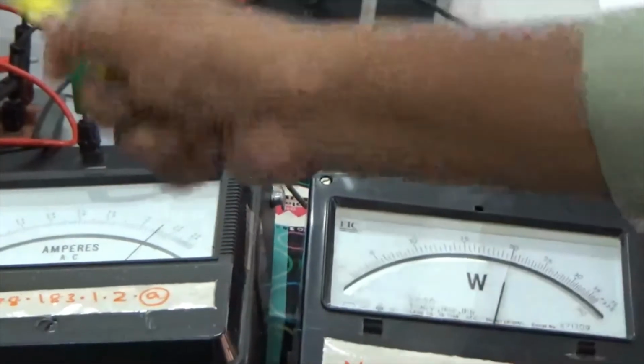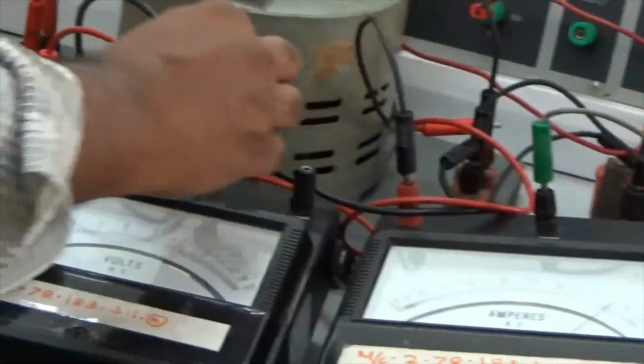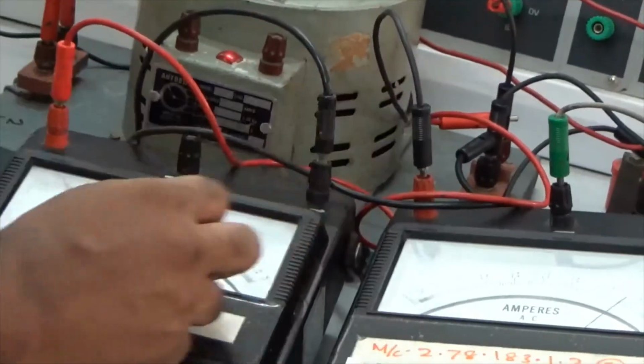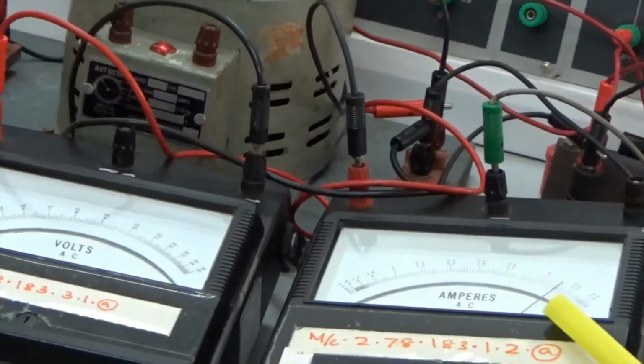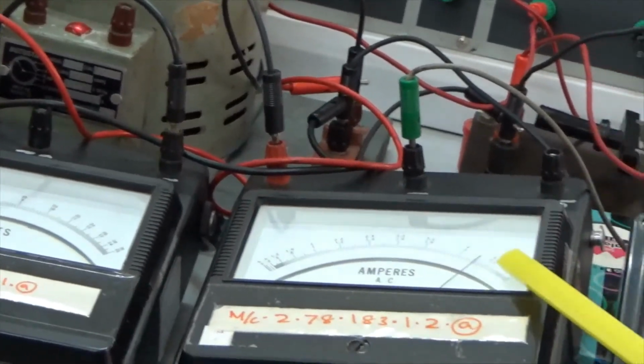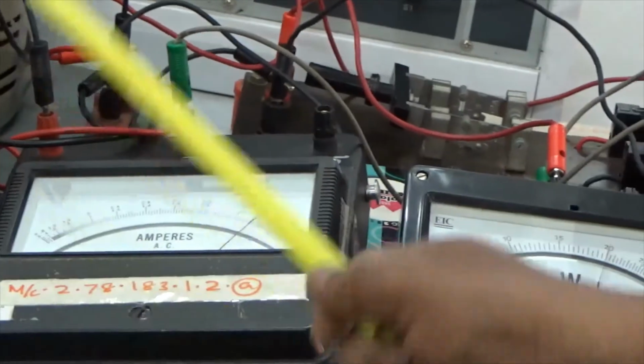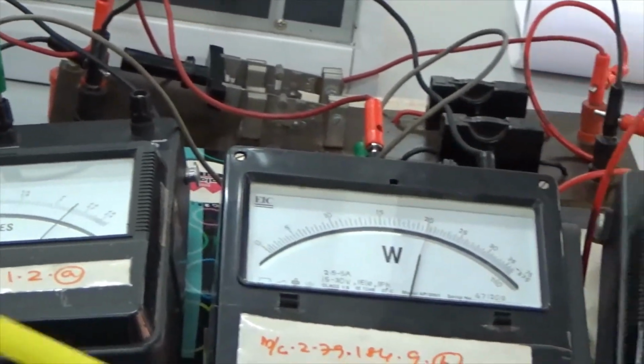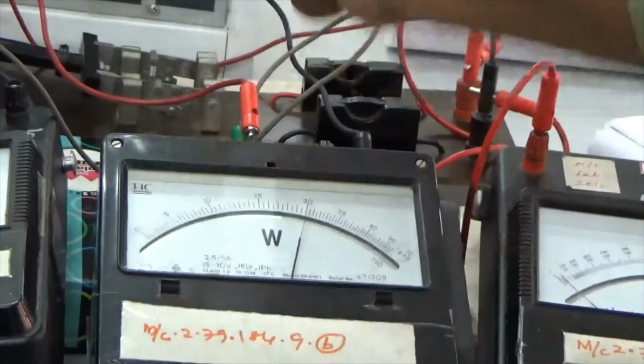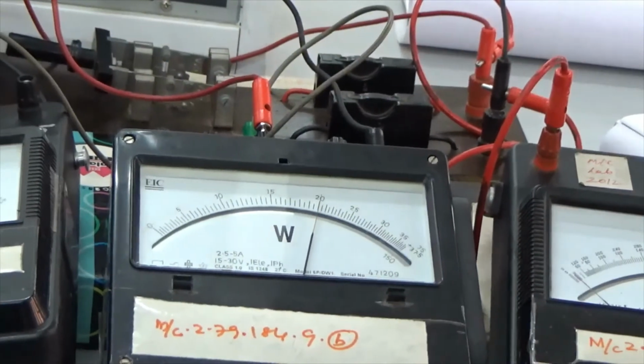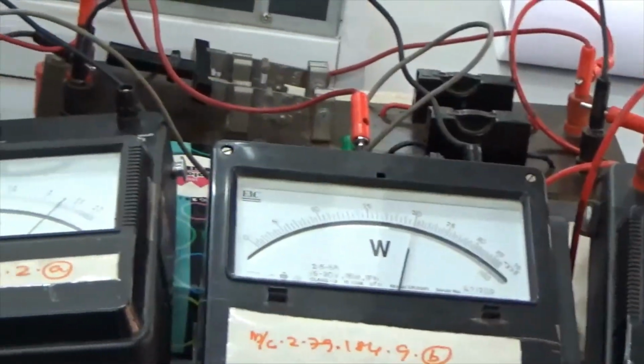This takes a low voltage, approximately 0 to 8 volts at maximum, so with a small voltage you can inject the rated current. Because the series secondaries are shorted, the same current flows through the two transformers. So this is nothing but a short circuit test, and at that time you note down the wattmeter reading.